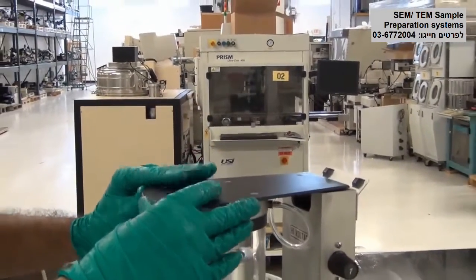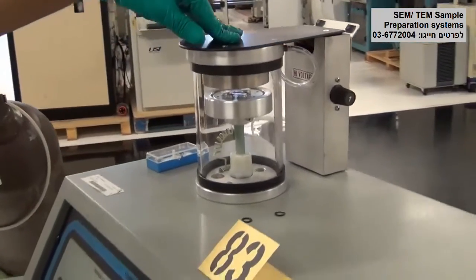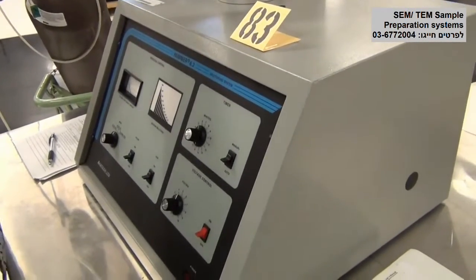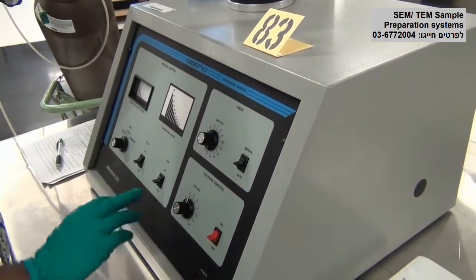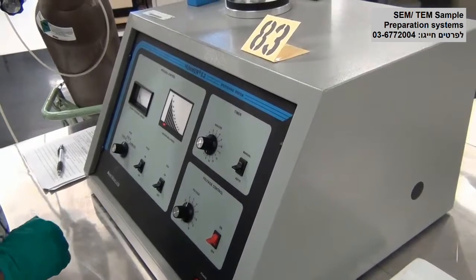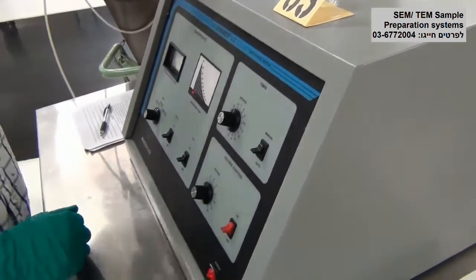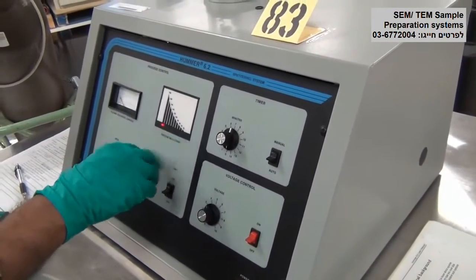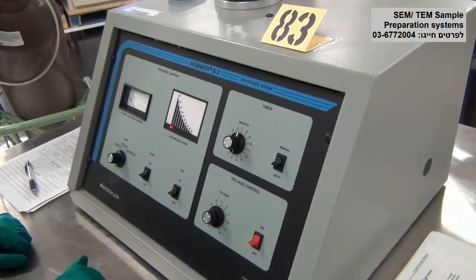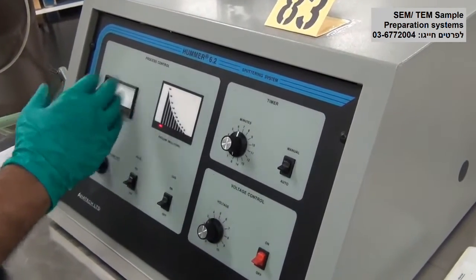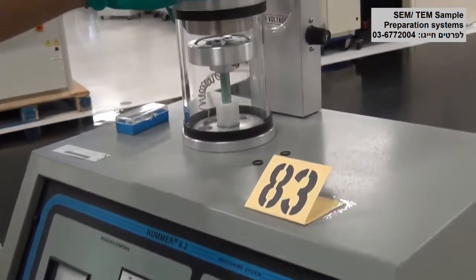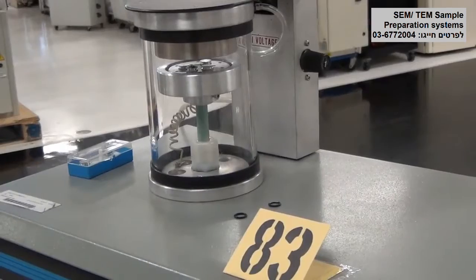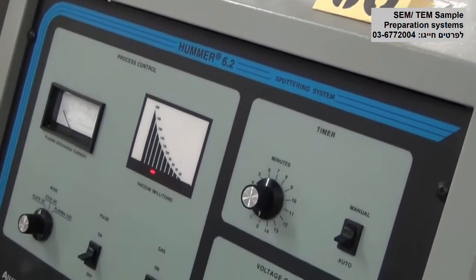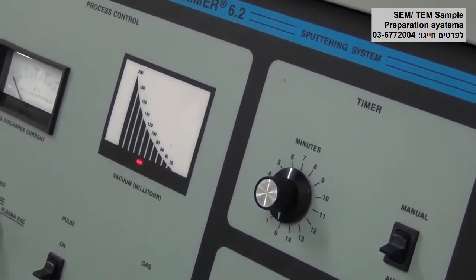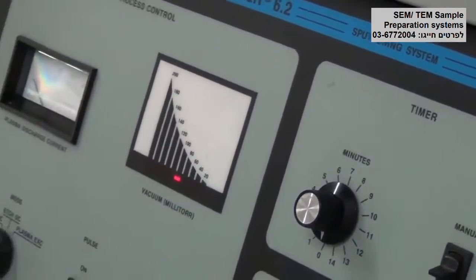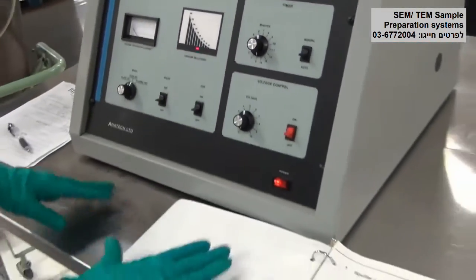And to start the unit, close the chamber door and turn on the power. As soon as we turn on the power, the pump down begins. So make sure the gas valve is off, and once the pumping starts, the indication is from 200 millitorr down to 20 millitorr. It takes about a couple of minutes before the chamber vacuum level reaches to about 20 millitorr. We have a detailed user manual to assist the operator.